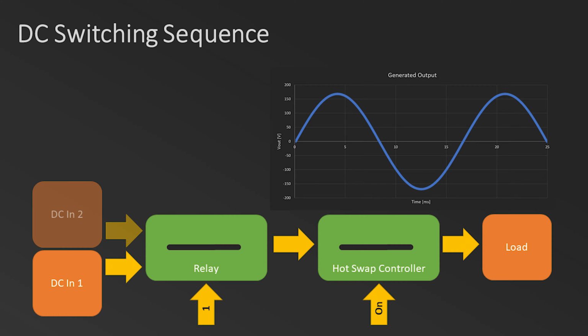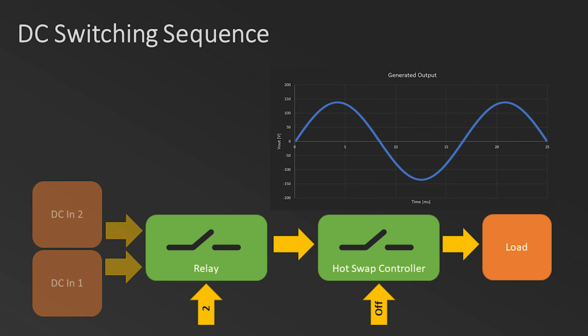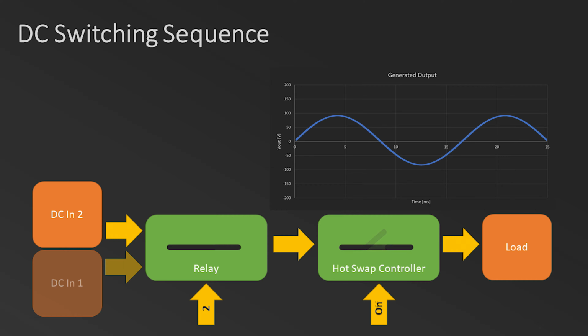This is the procedure that we need to follow if we want to leverage the full benefit of our hot swap controller. First, we'll cut power to the downstream load by disabling the hot swap controller. This will greatly reduce the current through the relays. In fact, it will bring it down to 0 amps. Now we'll actuate the relays to switch the other power source. This will connect either the primary or secondary power input to the input of the hot swap controller. We can now safely power on.